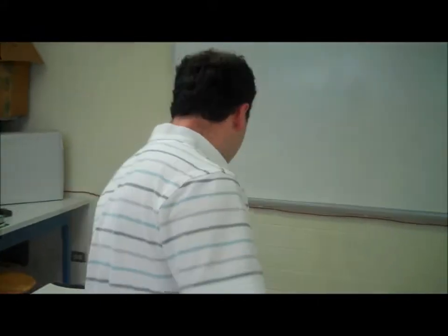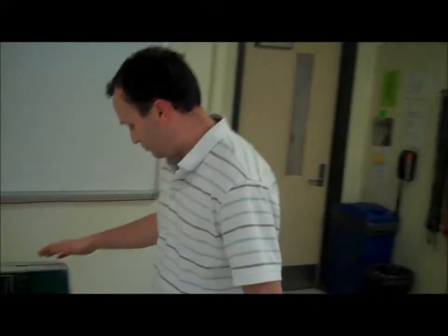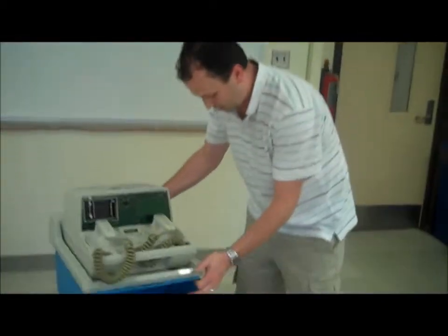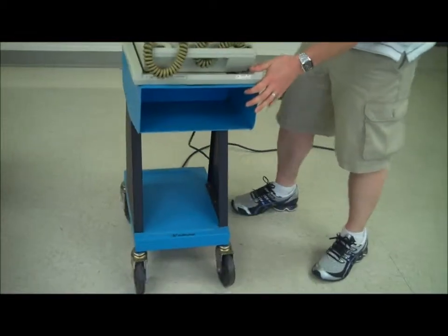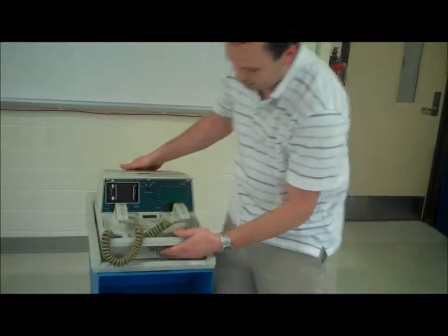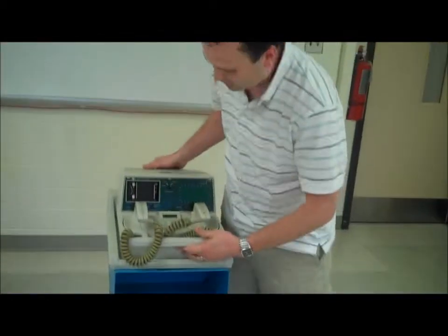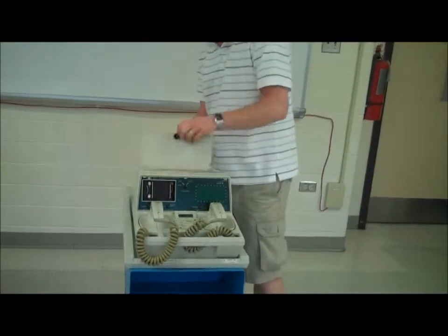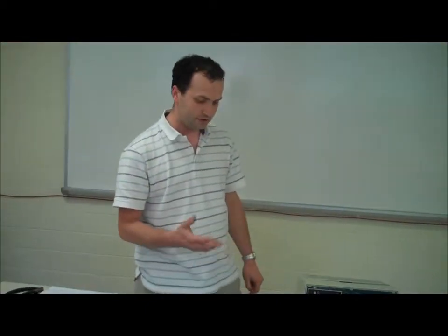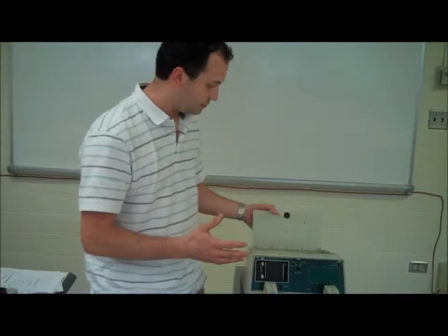So the first step I'm going to do is a visual inspection of the defibrillator. Just to make sure that the cart is rolling smoothly and it looks like the wheels are all working okay. And I want to look at the case, make sure there's no cracks, it's not been dropped. Everything looks fine on that. And if it does have batteries, you want to see if the batteries are in the case, and you can check the batteries as another visual inspection.